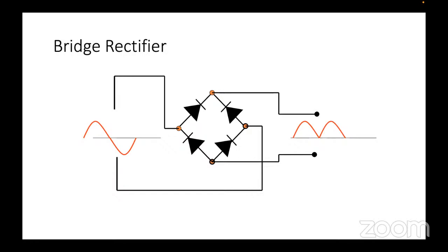Okay. And that is again an important part, which is, diodes are an important part of defibrillators for this reason. They need to have the current flowing in one direction, and it needs to be constant. So that's why rectifiers are an important part of the bridge of the defibrillators.